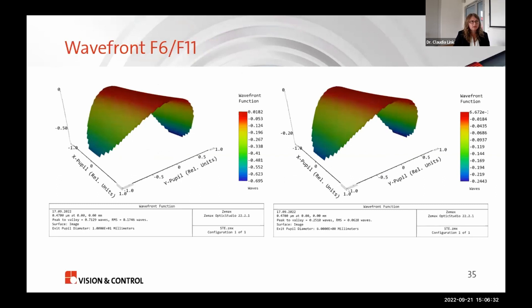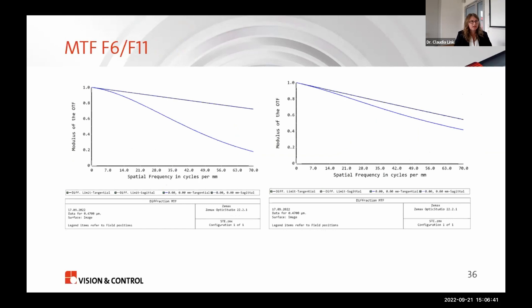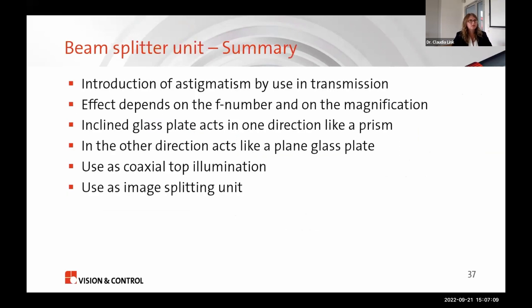Looking at the wavefront and MTF: at F/6 you can clearly see the astigmatism — one direction is diffraction-limited and the other is quite degraded. Stopping down reduces this effect significantly. To summarize: the beam splitter unit introduces astigmatism when used in transmission, and the effect depends strongly on the F-number and also on the magnification — the higher the magnification, the larger the effect. An inclined glass plate acts as a prism in one direction and as a plain glass plate in the other.